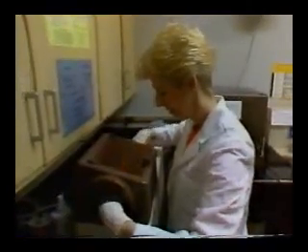Having an automatic processor does not guarantee good results in film processing. Automatic processors demand rigid scheduling for replenishment and replacement of chemicals. Routine preventive maintenance is required in order to produce films of consistent high quality. Frequent cleaning of the rollers is a must to keep your films clean. Replenishment and replacement schedules should be posted and monitored in your darkroom or near your automatic processor.